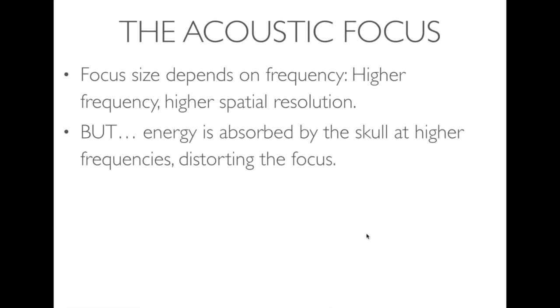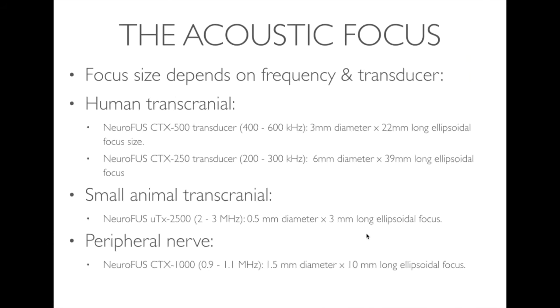There is a bit of a caveat to the size of the acoustic focus. If you increase the frequency of the ultrasound delivered by the transducer, you get higher spatial resolution - as frequency goes up, the size of the focus goes down. But when you put the transducer on a real person's head and the ultrasound travels through the skull, the higher the frequency, the greater the rate of energy absorption by the skull. That does two things: the absorption of energy causes the ultrasound energy to scatter in different directions, which means the focus gets distorted or even moved around. Also, delivering a pulse at an incredibly high frequency can increase the temperature of the skull, which we ideally want to keep to a minimum from a safety point of view. So there's been a compromise between the spatial resolution that can be achieved and the frequency of stimulation that can realistically be delivered, regarding distorting the focus or heating up the skull.